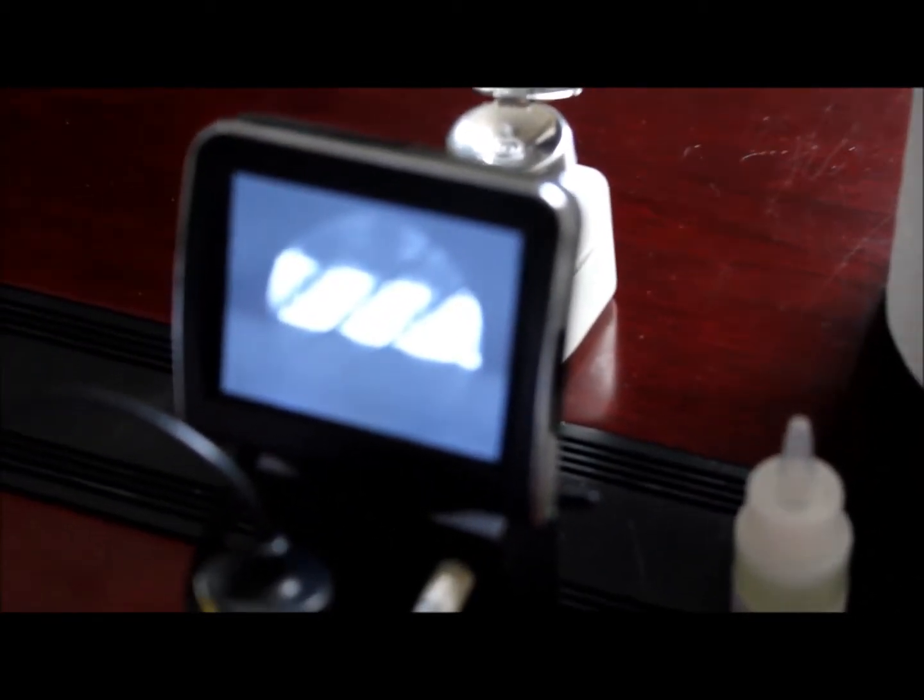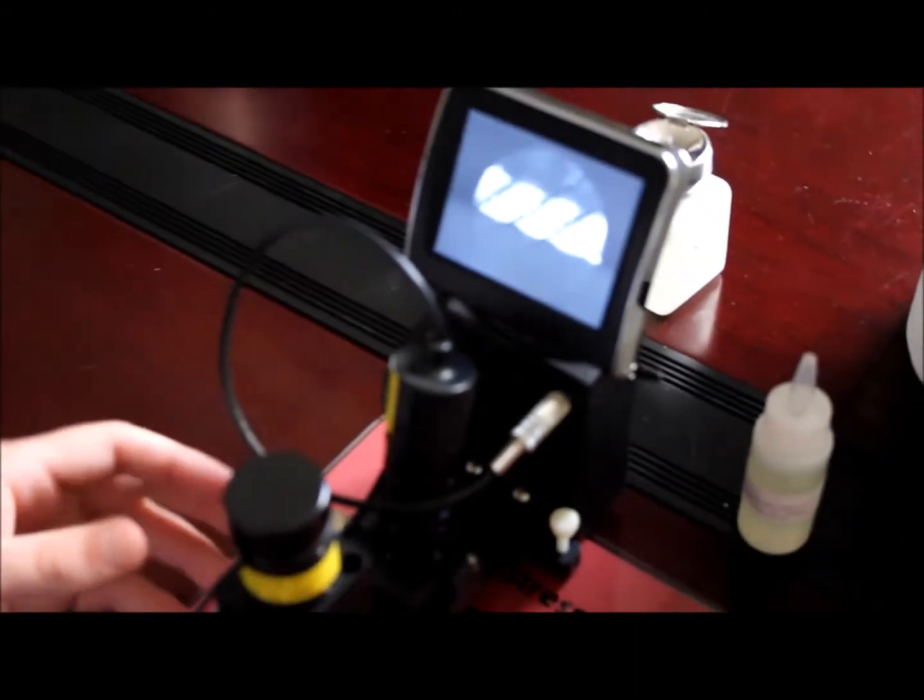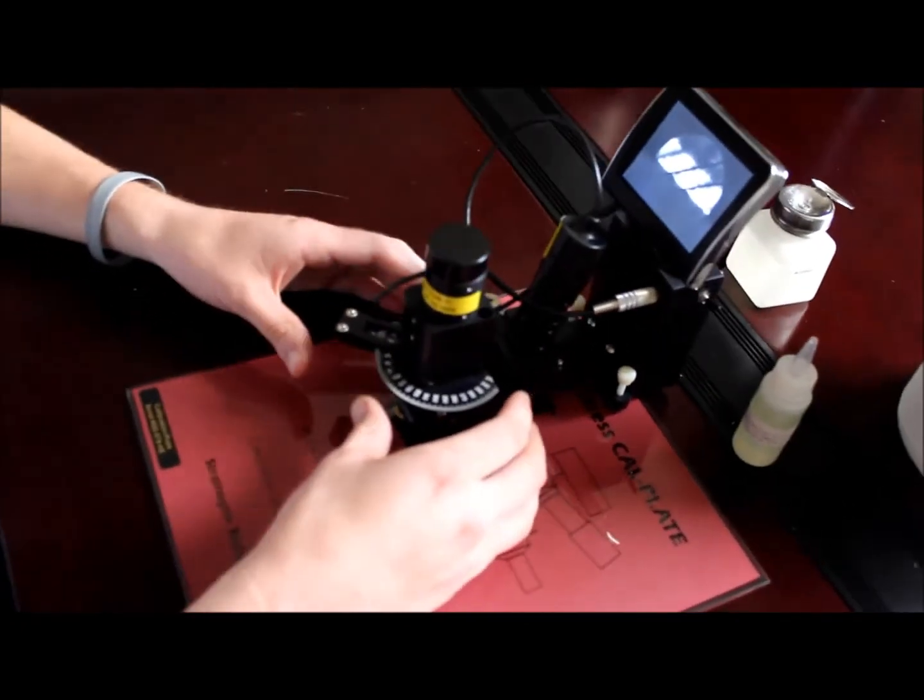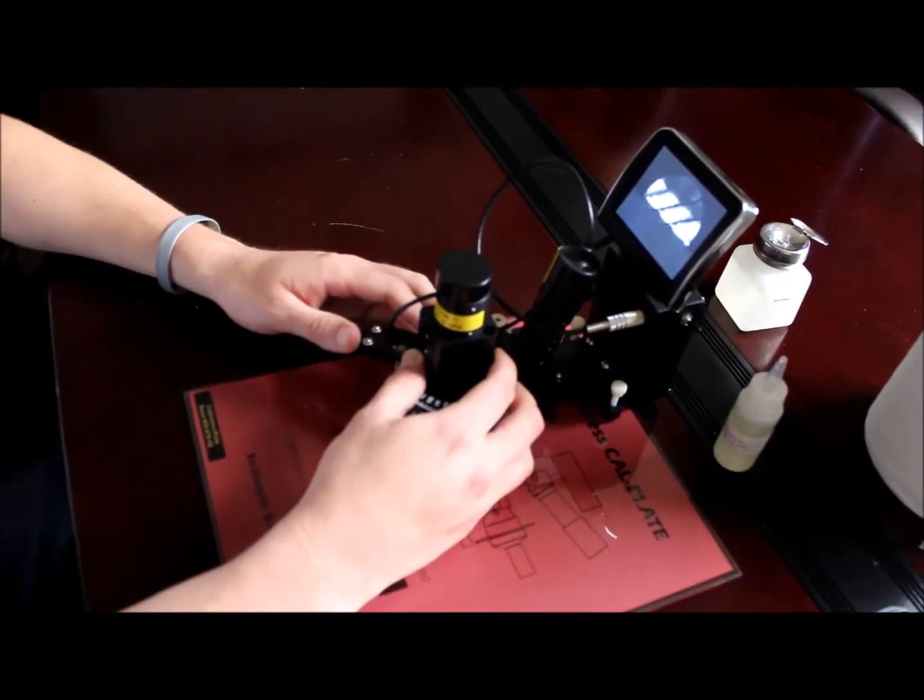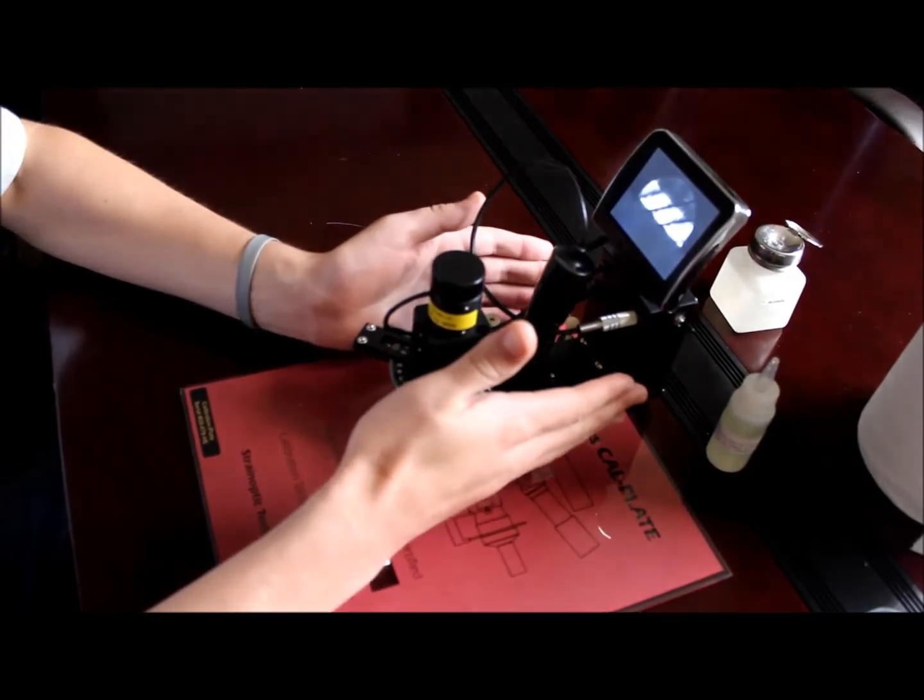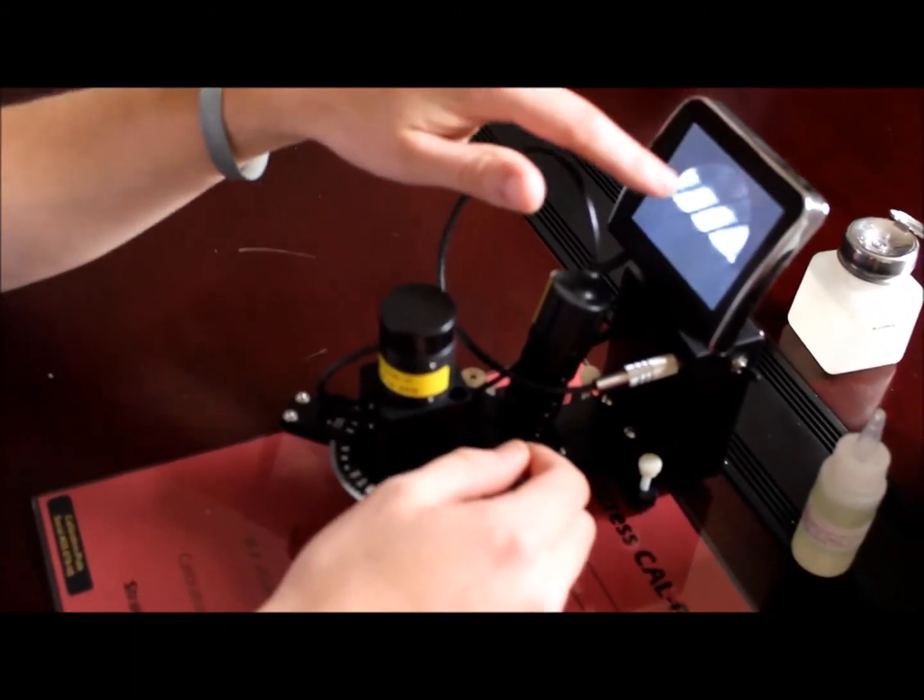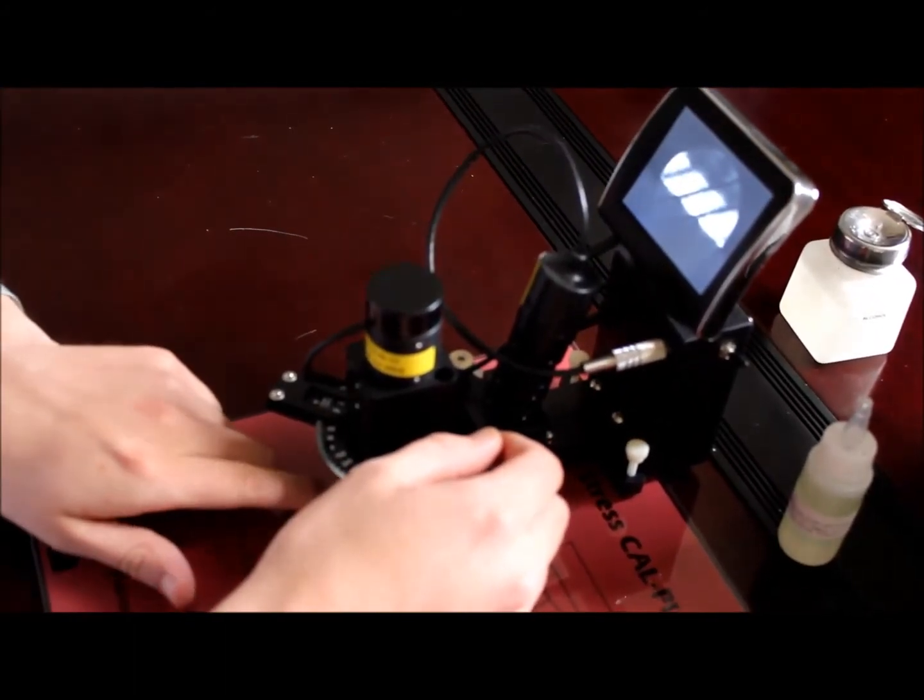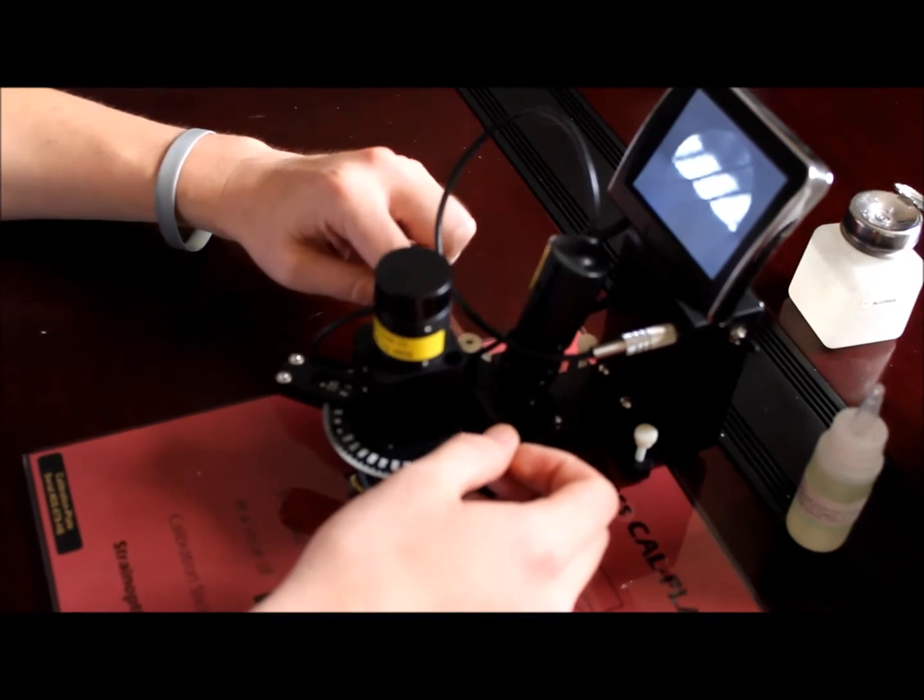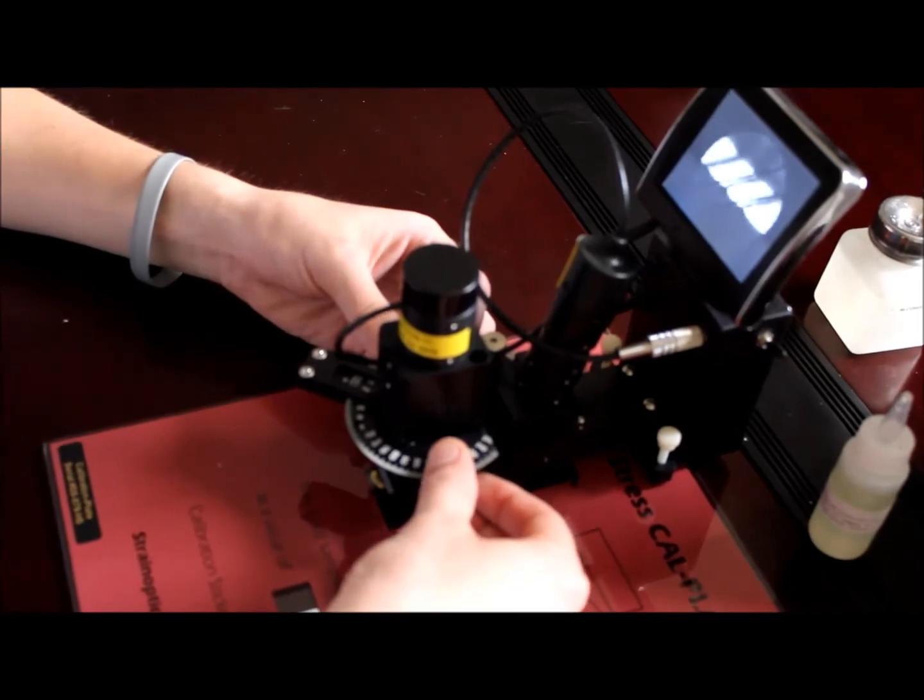So what I've done so far is I've set the location of the eyepiece directly above the mirror. I've set the laser so that it's in a ballpark for where it should be. I've put the instrument on the glass and while holding it in a way that it was level, I then set the leveling screws back here to allow it to actually stay in a stabilized level area. Once I did that, I looked for light somewhere within this eyepiece. And then I changed the mirror until we got a bright image there, at which point I changed the tilt assembly on the laser until fringes became robust and easy to see.